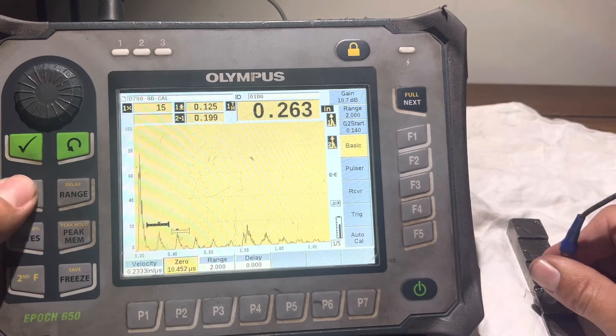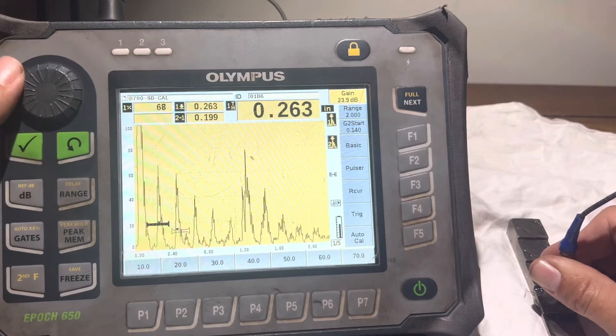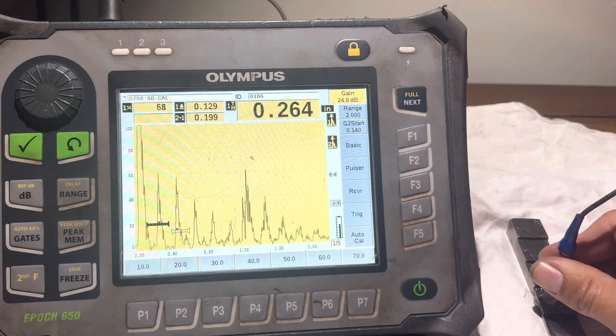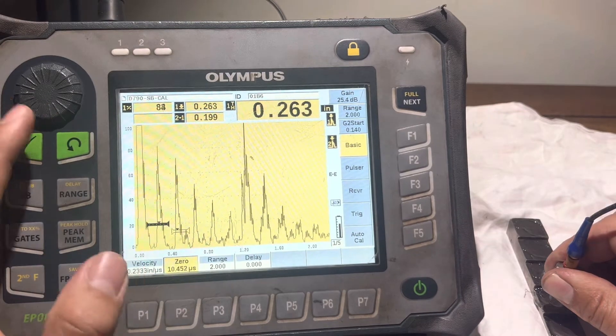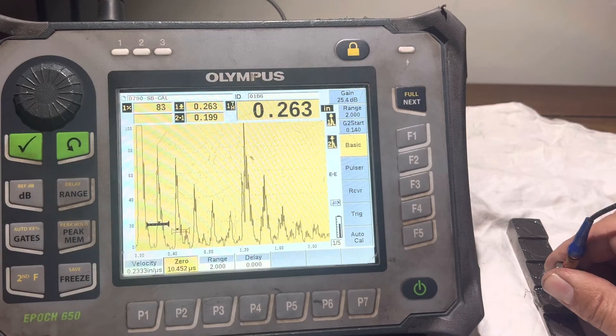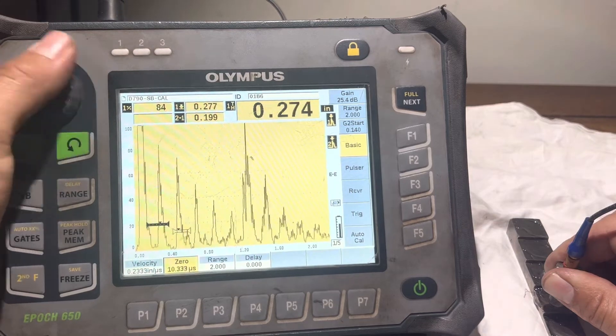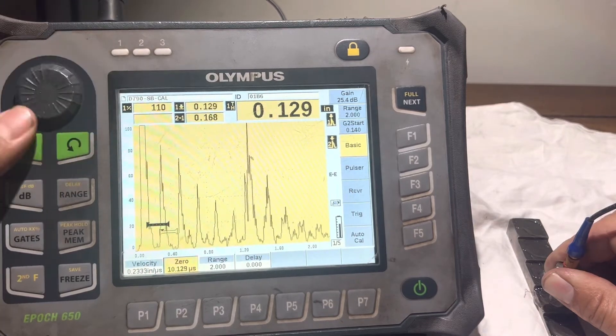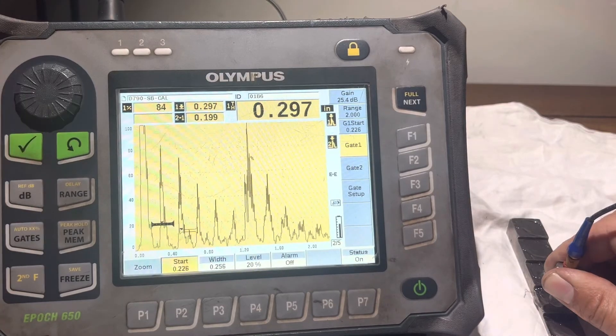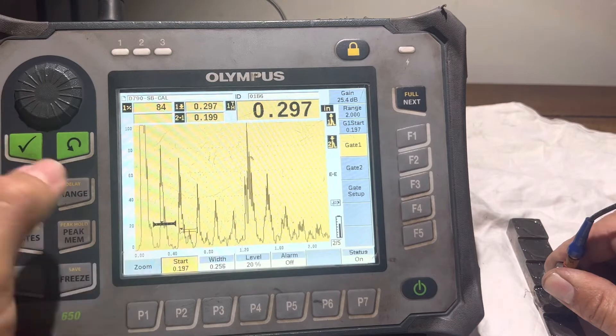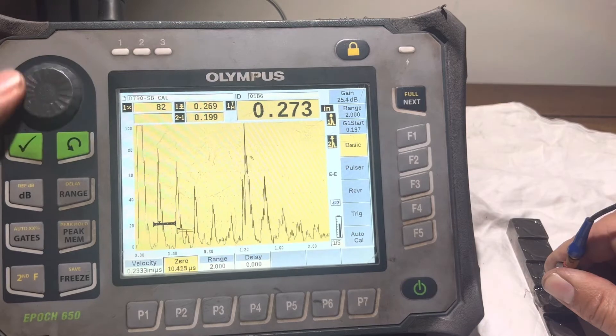So I'm placing my transducer into the 2 and I'm going to increase the gain. You can see it's out of range, my 2 is good, my echo is good. And what I'm going to do is I'm going to move my zero into place. I'll make sure that I'm following the actual peak so it moves. So there we go we're on track.